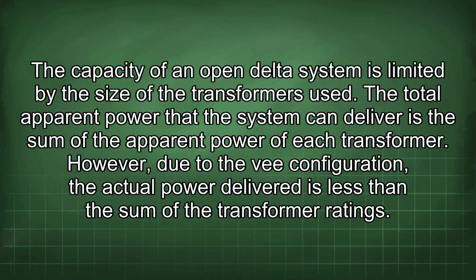The capacity of an open delta system is limited by the size of the transformers used. The total apparent power that the system can deliver is the sum of the apparent power of each transformer. However, due to the V configuration, the actual power delivered is less than the sum of the transformer ratings.